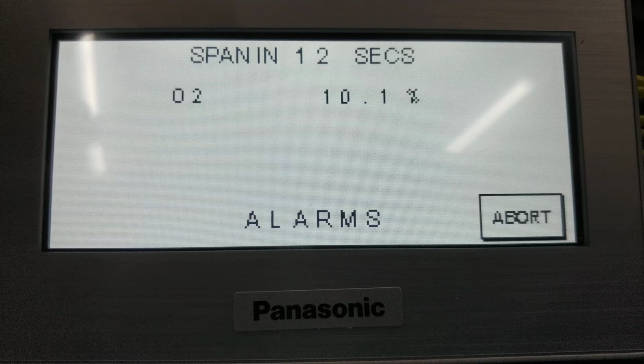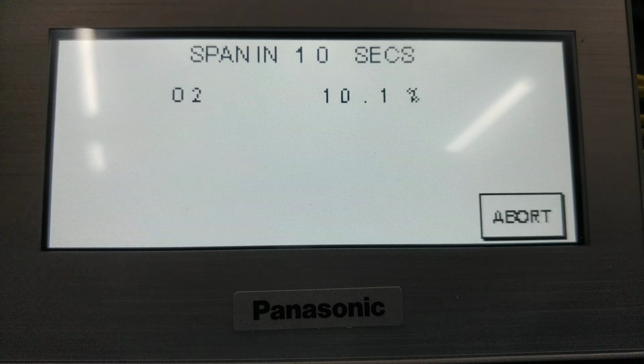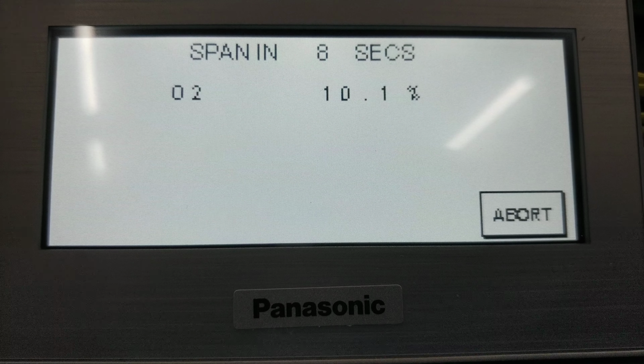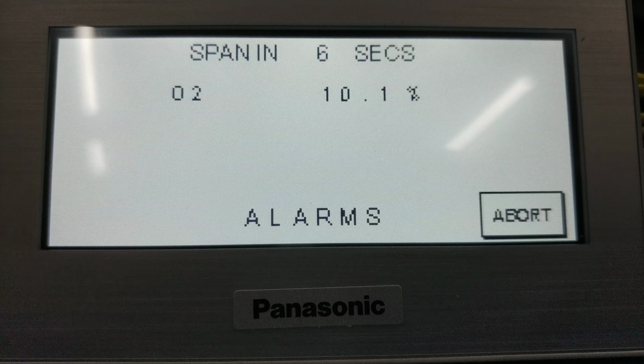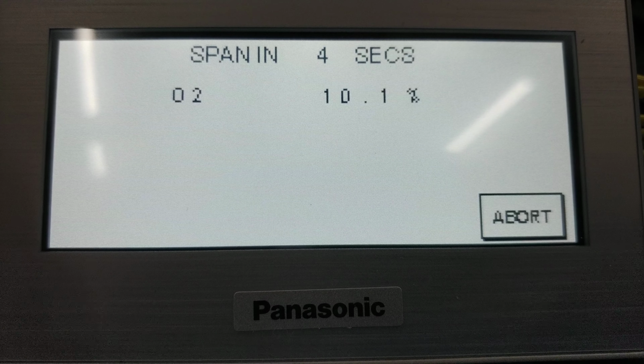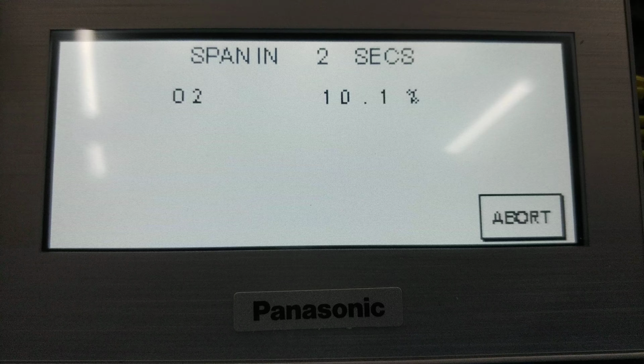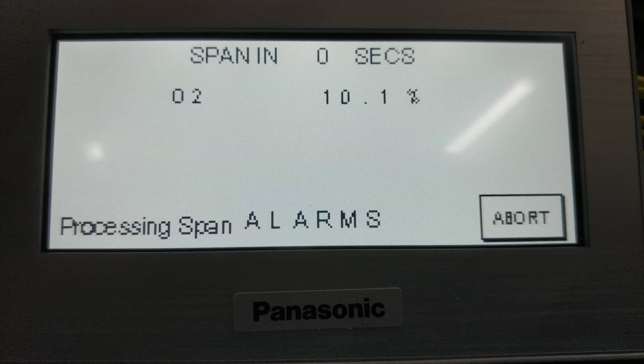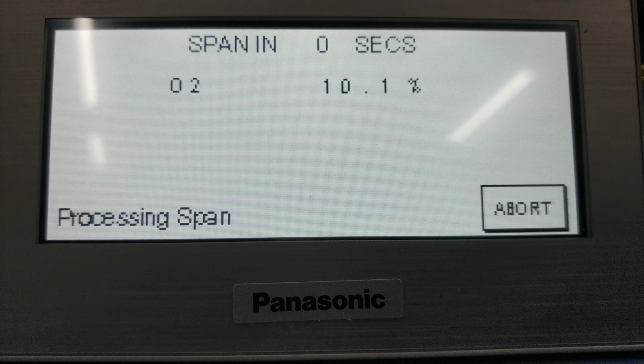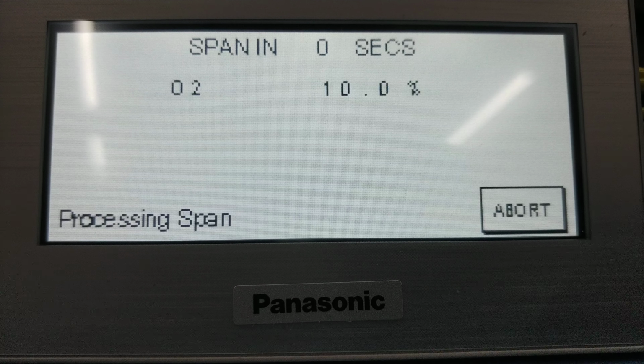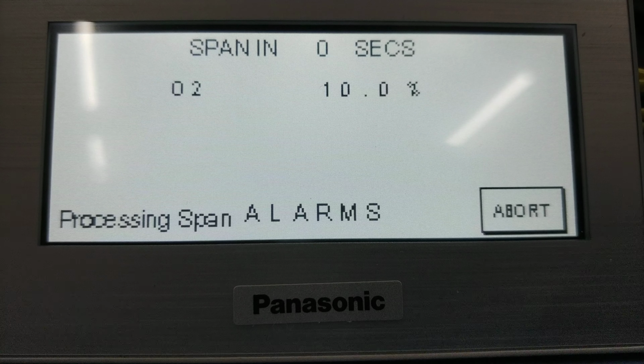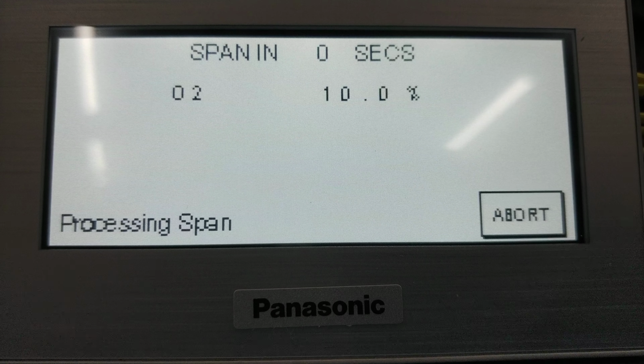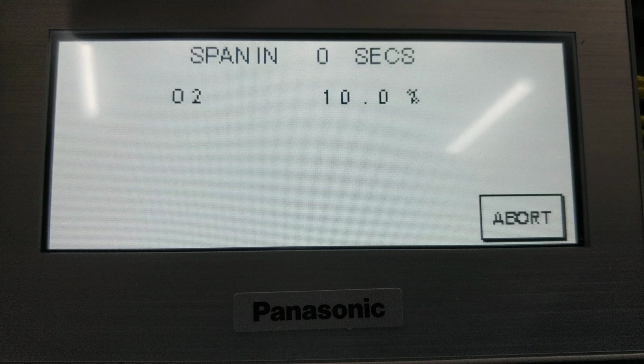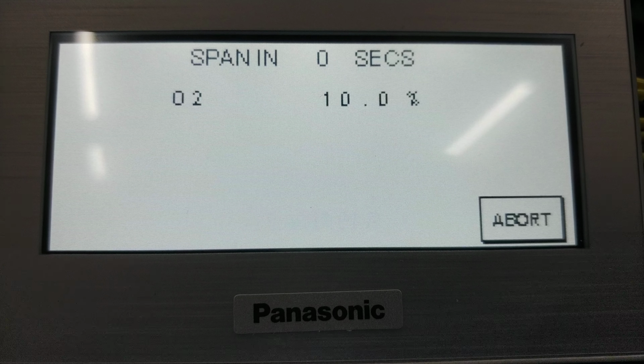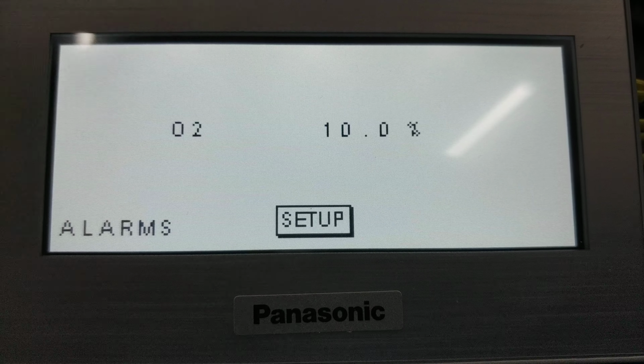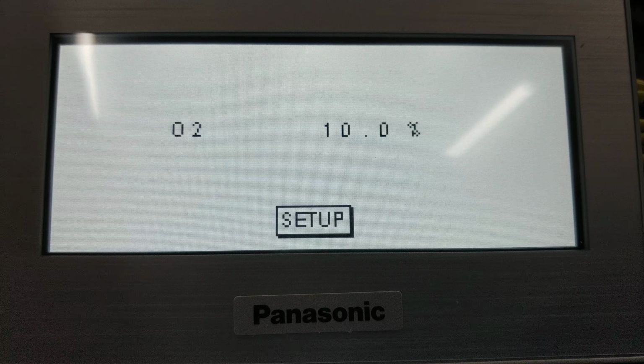Don't worry about this gas alarm right now. It's alarming because our gas alarm has been set to 2%. Since we're running above 2% oxygen in the sample stream, you're going to see this high gas alarm. So we're just going to let it do its thing. So there you go. You see it just processed it to 10% there. Okay, so now our span calibration is done.